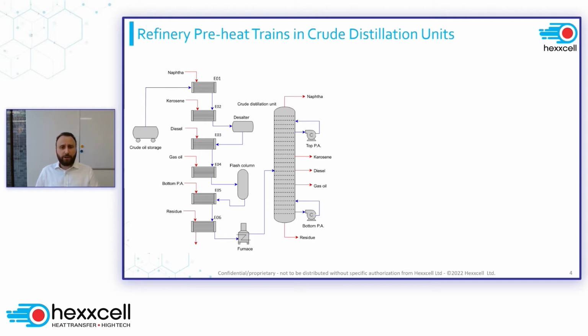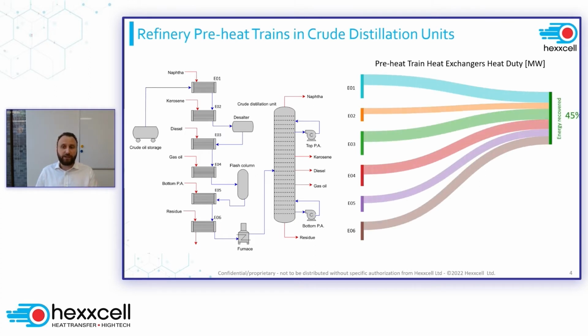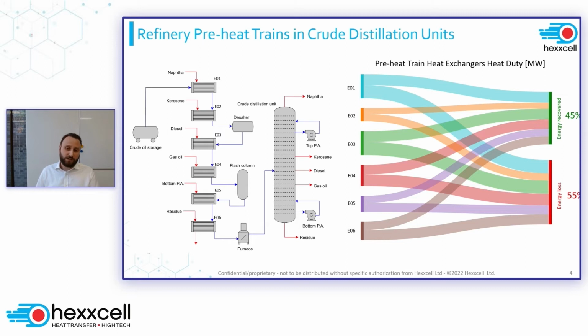What we typically do with our customers is look at a breakdown of the individual heat exchangers and see how they contribute to the overall duty supporting the furnace - how much duty is recovered from the hot streams at the distillation column in each heat exchanger, how much duty is lost at individual heat exchangers, and what the total amounts to.